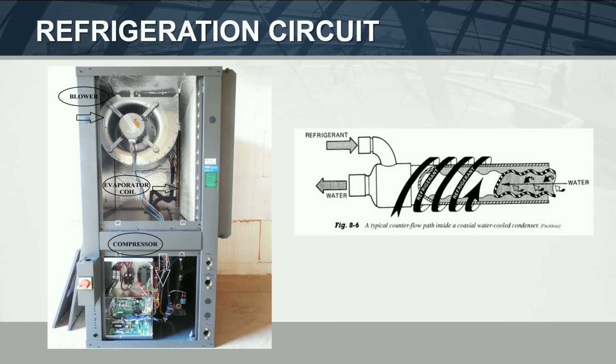That heat energy goes through this graphic here. This is a cutaway of a coaxial heat exchanger. If you're interested, I have one up here you can look at. Basically, water flows through the middle, and the refrigerant is around it on the outside. So this is where the heat exchange happens. I think this is probably the most confusing part of geothermal: how do you get 70-degree air out of 50-degree ground? What does the heat exchanger look like? It's a metal. We use copper or cupronickel. Water flows through it. It's rifled, so you get turbulent flow, and refrigerant flows around it so we can extract the heat.